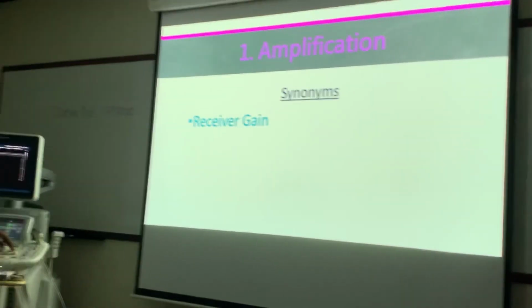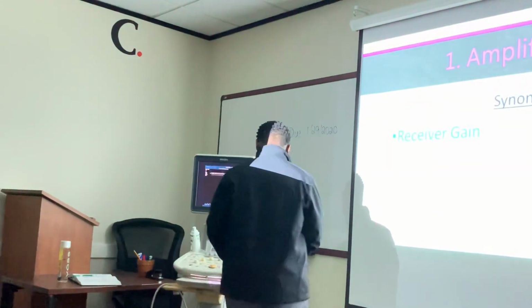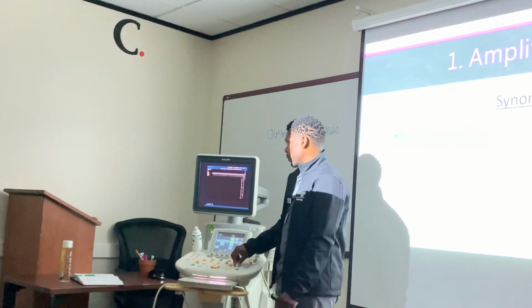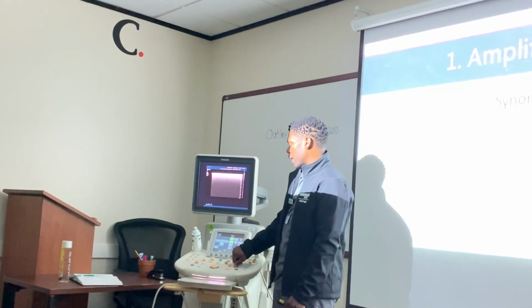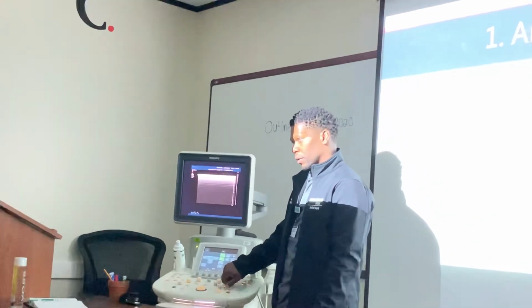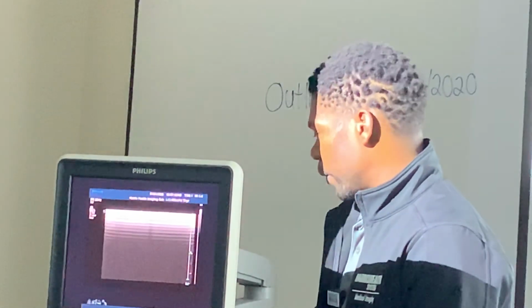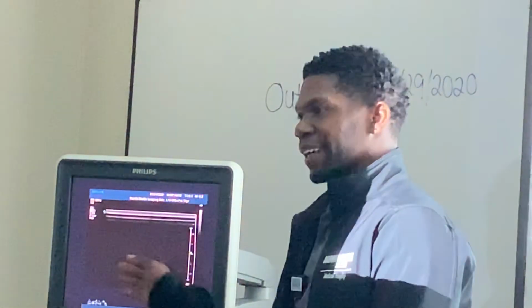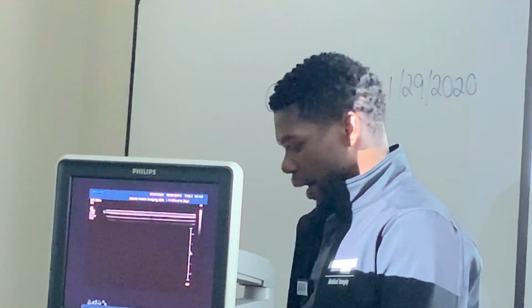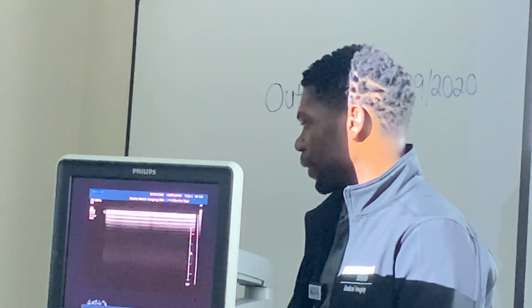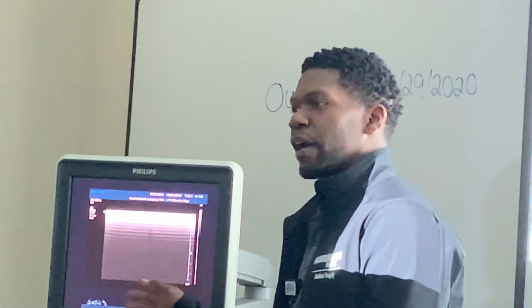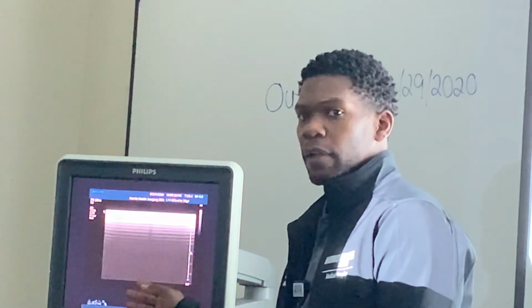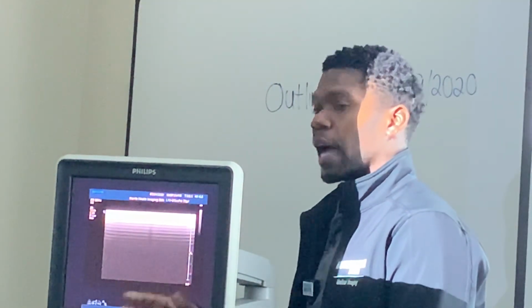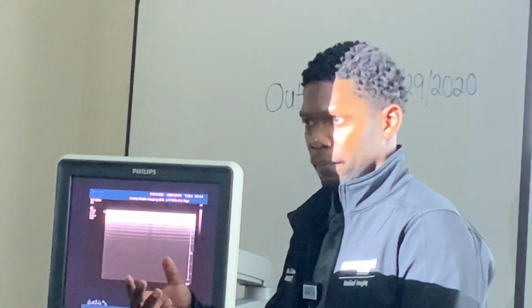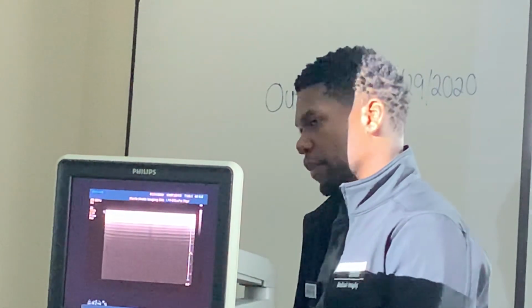So when I have my receiver gain, you guys, let's check it out. My whole image is getting bright to the same degree, right? Like when I have it down, I don't see anything in the far field, right? That's why it takes so long for me to see anything, because it's not like it's going to amplify the far field faster than it amplifies the near field. It's going to amplify it to the same degree. Okay? So that's why it appears that way.